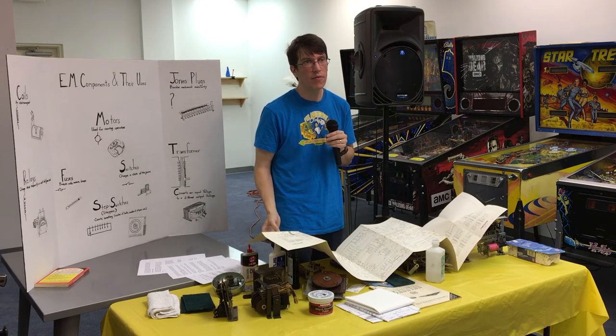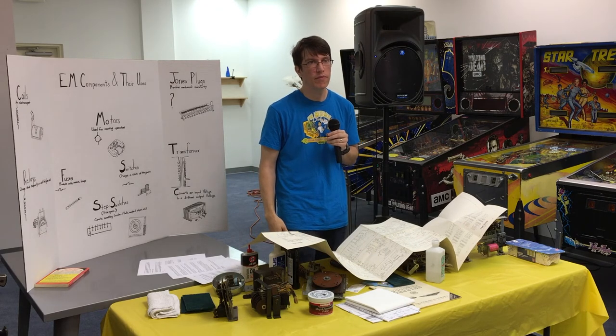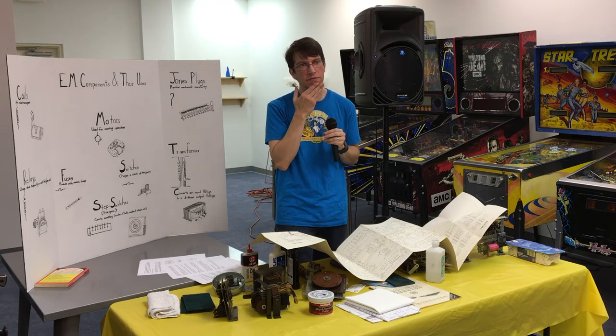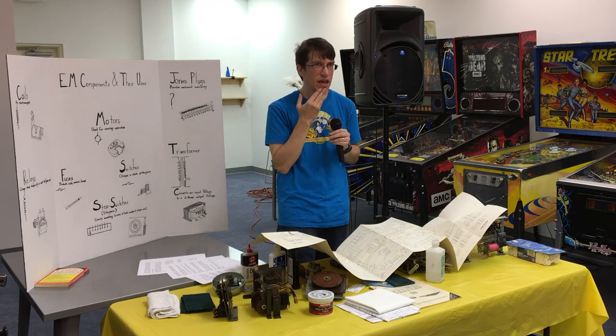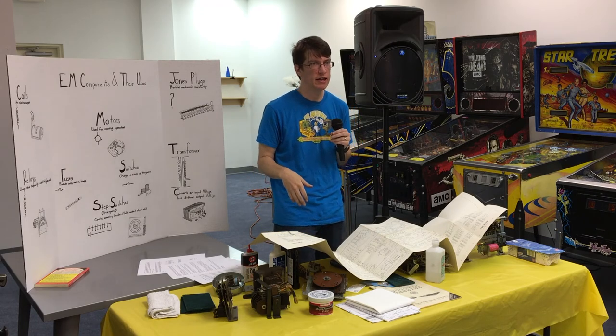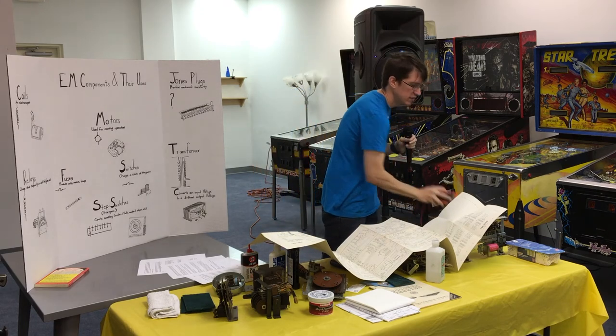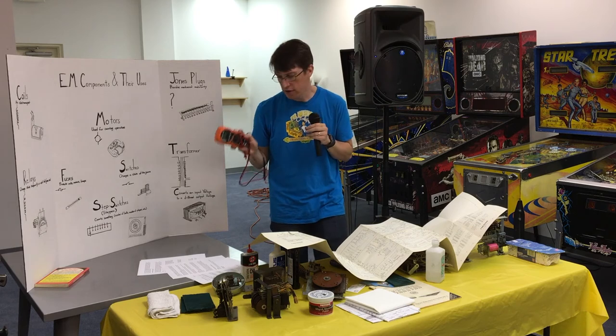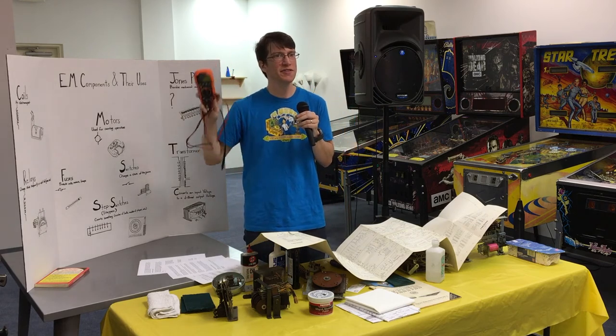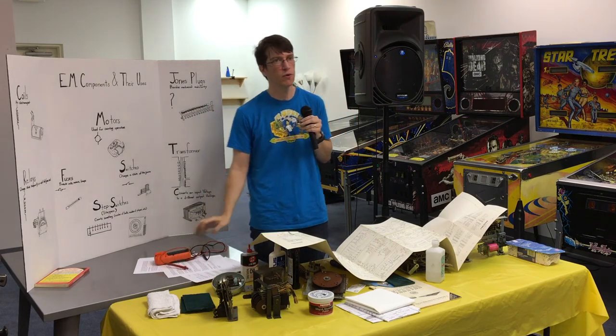Can you use a continuity tester on either side of the Jones plug to see if the corrosion is causing the problem? Yes, but in the example I gave, sometimes that's not enough because the amount of voltage present is too low. So yeah, it'll conduct this, but it might not conduct full coil voltage.